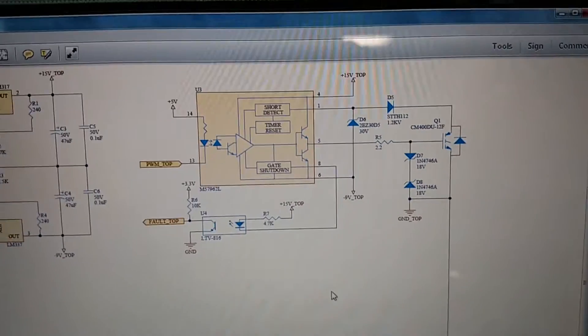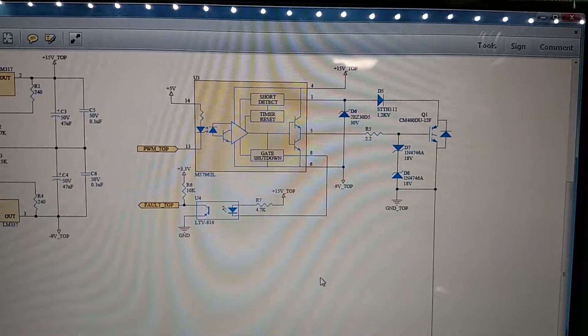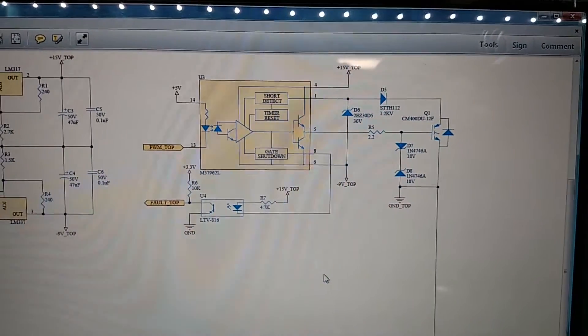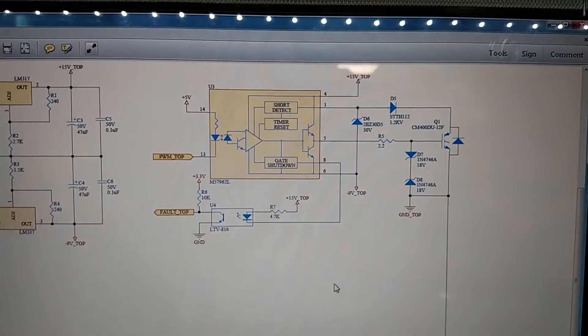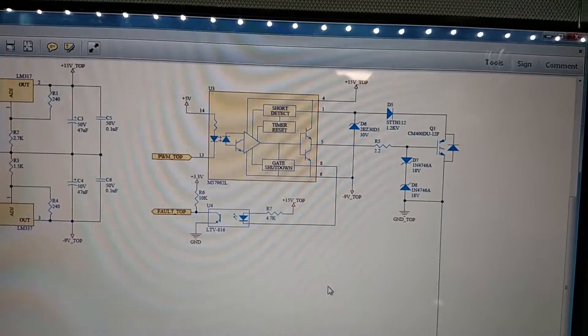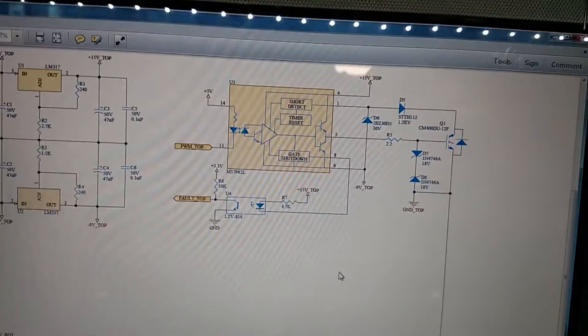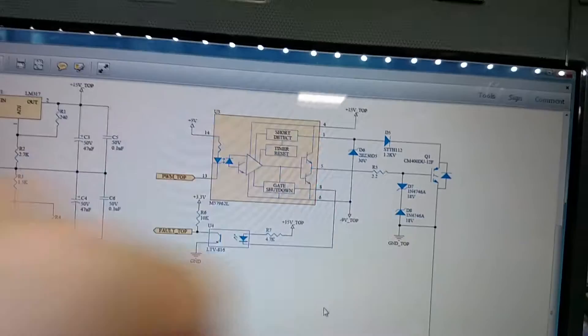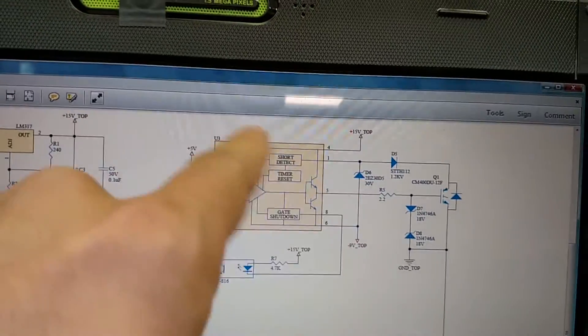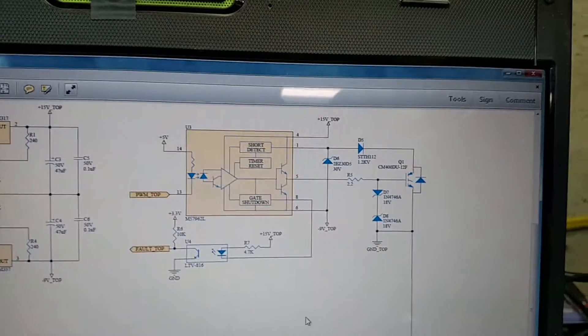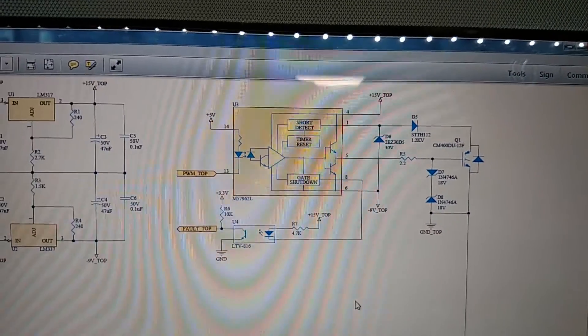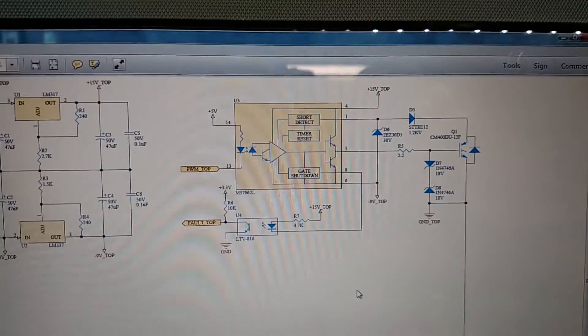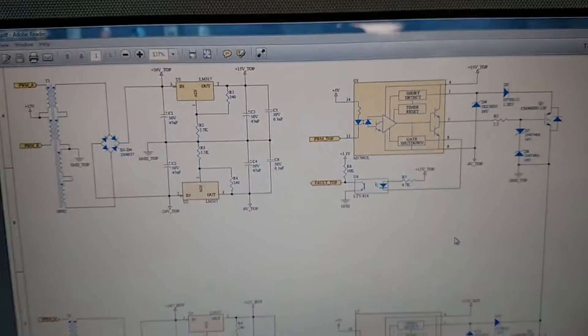And I think there might be a video. If you look back through all the videos that I've posted, there's one where one of the IGBTs in a, I think it was on a UMOC 445 that I was working on, there was a short on one of the legs. And so every time it turned on, it made this horrible squealing noise. And that's because it's sitting there being told to turn on full power. It's getting hit. And then this guy's shutting down and it just sits there and oscillates because this is like a one millisecond delay or something like that. Sends about one kilohertz just making a horrible squealing noise. This is dumping, trying to dump hundreds of amps through there or thousands, depending on what's going on.